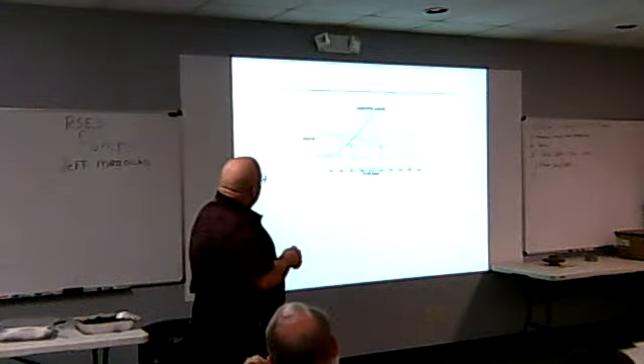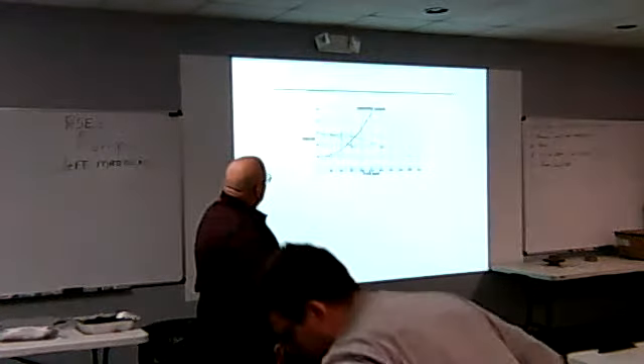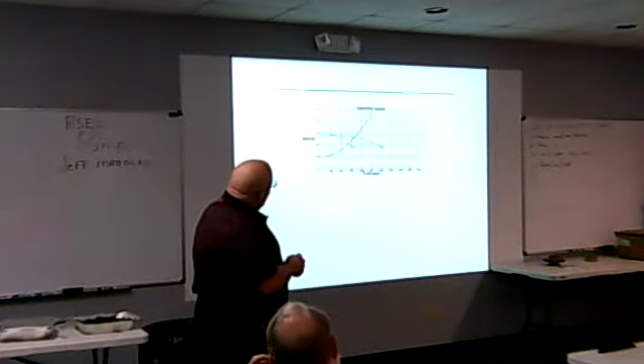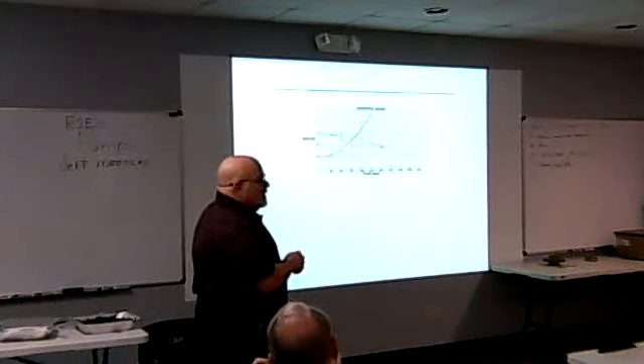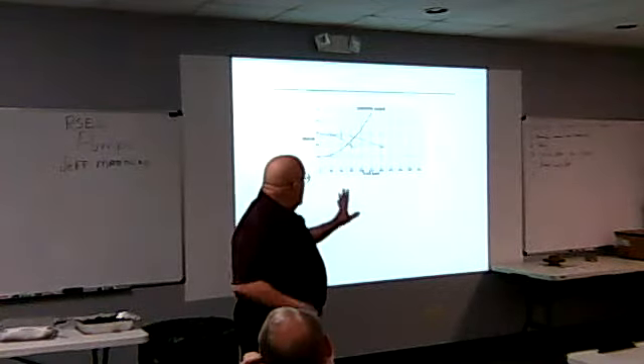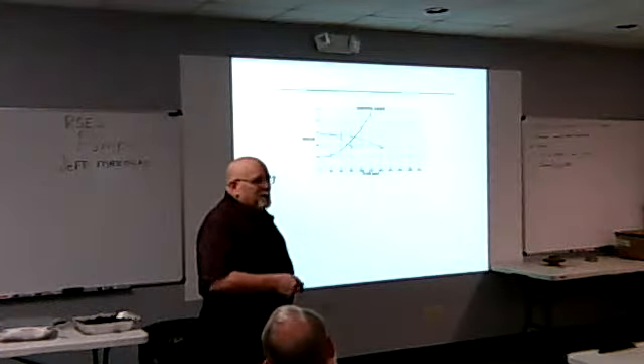What you do is take this impeller curve, and to draw this second curve, you say, okay, I've got 88 feet of head at 300. So I go out here and put a mark at 88 at 600. And I come back here and say, okay, I've got 600, and I go out here and put a mark at 1200. I come here and say, I've got a mark here at 900, and I go out here and put a mark at 1800. You can draw that second curve in. Once you lay your system curve in, here's my operation with one pump. I'm at almost 900 GPM. Here's where I'm going to get with two pumps. With two pumps, I only gain 100 GPM. Right. But if the head stayed the same... well, no, that's what I'm basing it on. I'm saying, based on the same head, yes. But my point is, they don't double. If you double the pump, you're not going to double the flow, because the head went up.